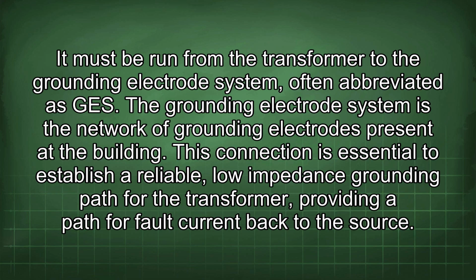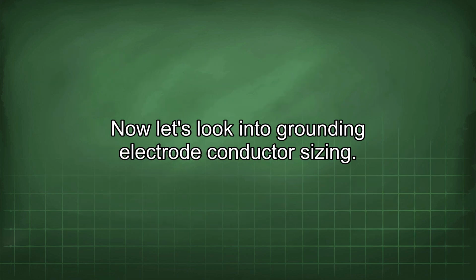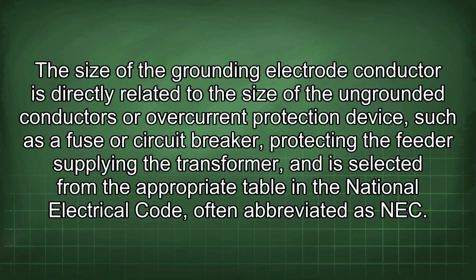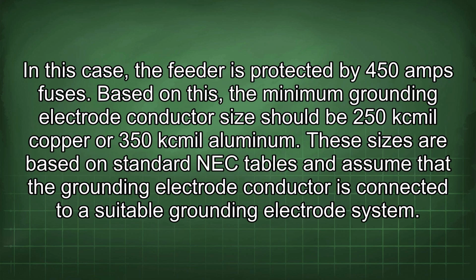back to the source. Now let's look into grounding electrode conductor sizing. The size of the grounding electrode conductor is directly related to the size of the ungrounded conductors or overcurrent protection device, such as a fuse or circuit breaker protecting the feeder supplying the transformer, and is selected from the appropriate table in the National Electrical Code, often abbreviated as NEC. In this case, the feeder is protected by 450 amps fuses. Based on this, the minimum grounding electrode conductor size should be 250 kcmil copper or 350 kcmil aluminum.